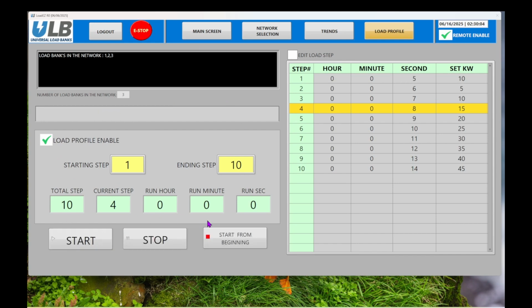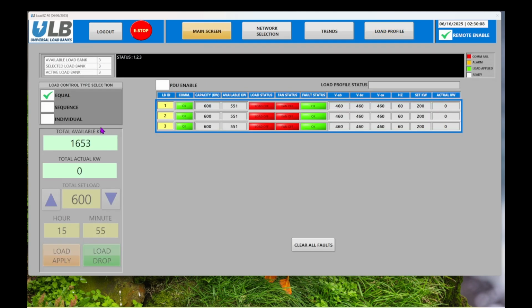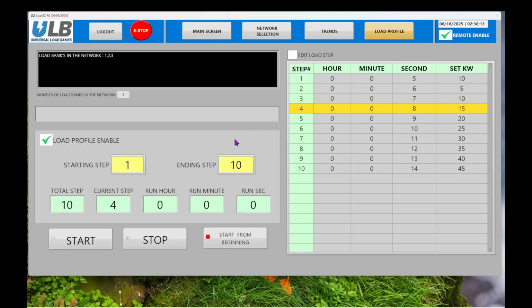To activate a load profile, on the main screen, select equal or sequence, press Edit Load. In each step, enter the time and kilowatt values manually or upload them using an Excel CSV file. Enable the load profile, select the start and end steps, then press Start. You can start or stop the profile at any time, and LoadEZ will show the current progress and status.